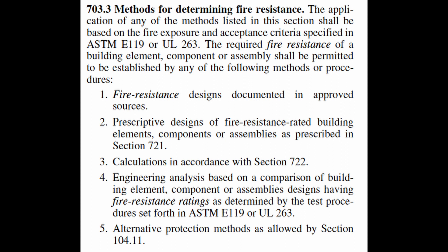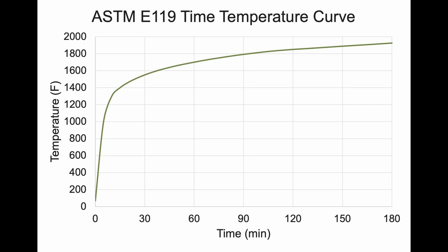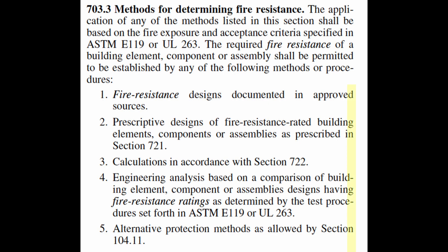So these are some common examples of when you might want or need to have direct applied gypsum wallboard to a mass timber member or assembly. How do you demonstrate this from a fire resistance rating perspective? From a code perspective, the building code gives us a number of options to demonstrate the fire resistance rating of a given member or assembly, referenced in section 703.3 of the IBC. All of these are based on the standard fire time-temperature curve associated with the ASTM E119 fire test standard. Within these options, you'll see things like documented fire-tested assemblies through approved sources, calculations based on section 722 of IBC, or an engineering analysis that uses data from an actual fire test to draw parallels.